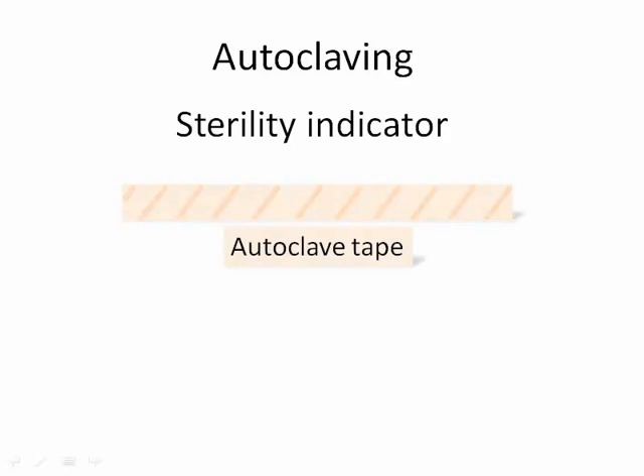To check that the autoclave is working and truly sterilizing, we use the sterility indicator, which is autoclaved with the load. Commonly, an operator uses autoclave tape, which is an adhesive tape that changes color when it is exposed to 121 degrees Celsius. Autoclave tape indicates that the autoclave reaches the correct temperature. The operator must verify the right amount of time has elapsed.